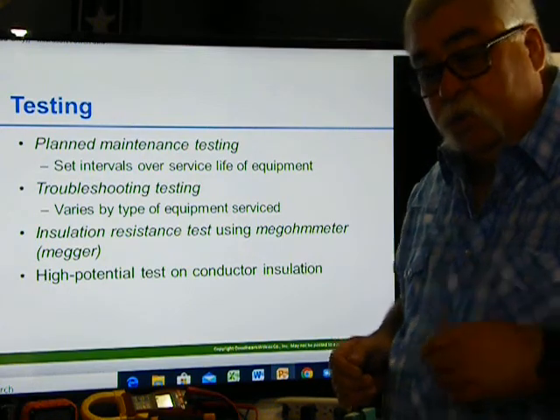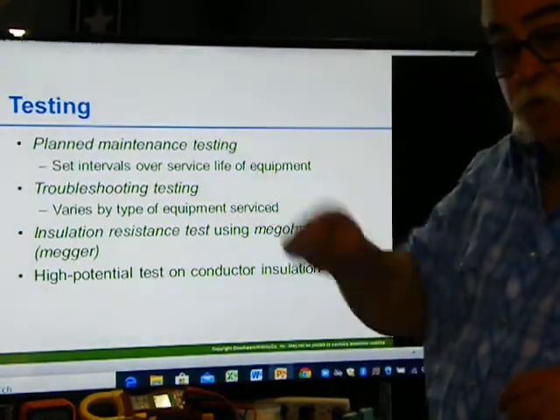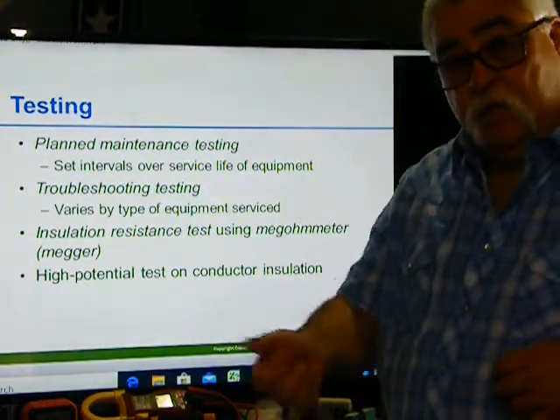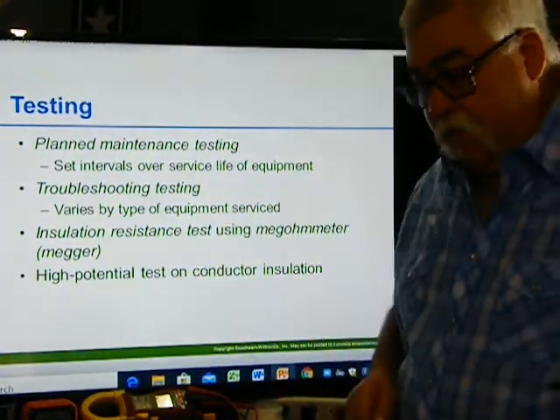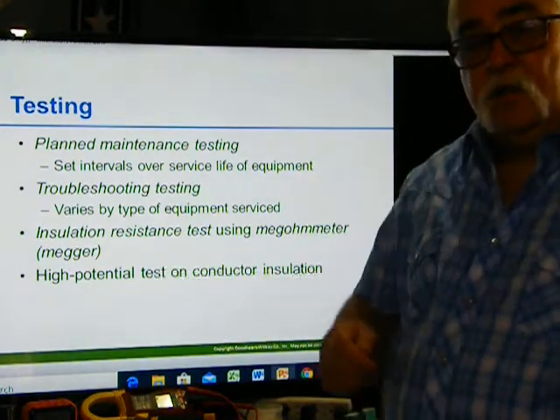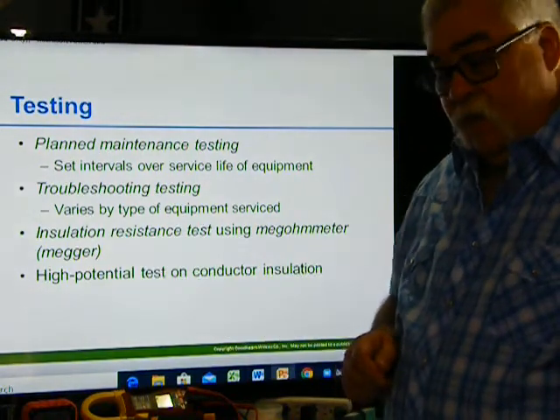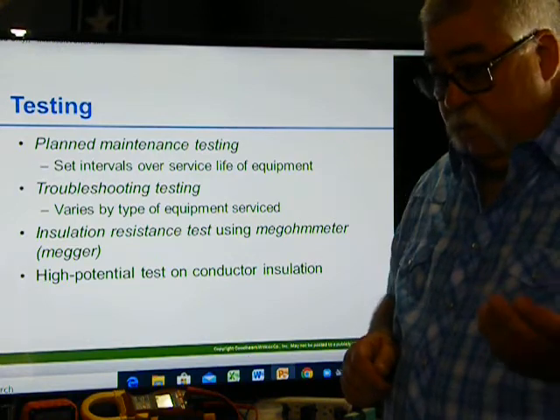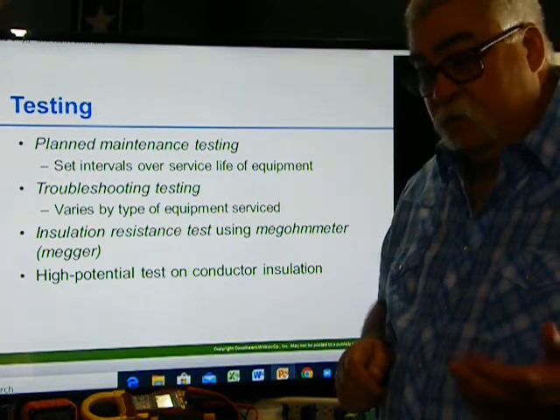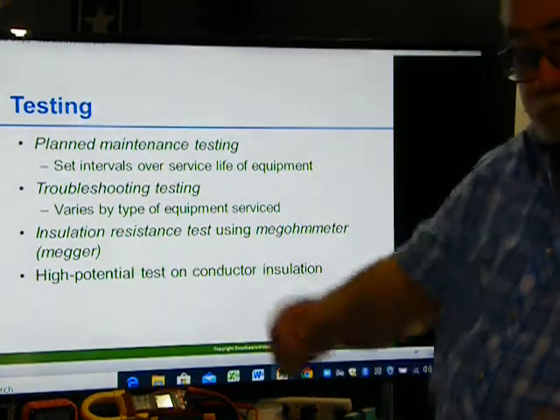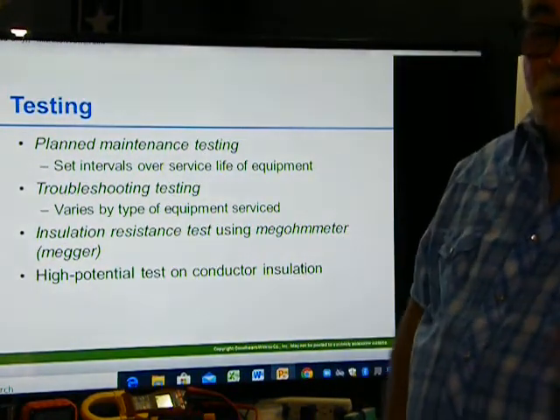We had to go around testing the receptacles every month, to make sure they're all working. I had a little GFI tripper that I would plug in and set. It had a dial, and it was made by Hubbell. You turn the dial, and it would trip, and make sure it trips, because they're all hospital grade. It had to trip at 4 milliamps. If it tripped past 4 milliamps or it didn't trip, I had to change it out.